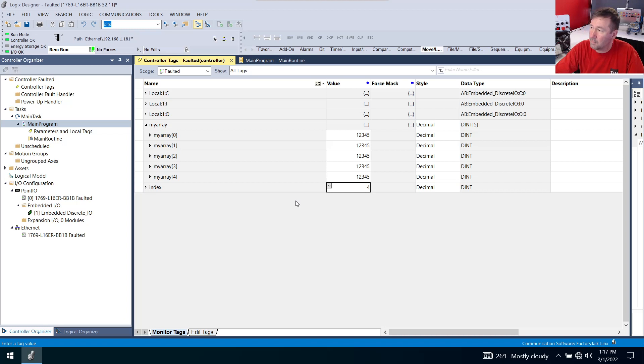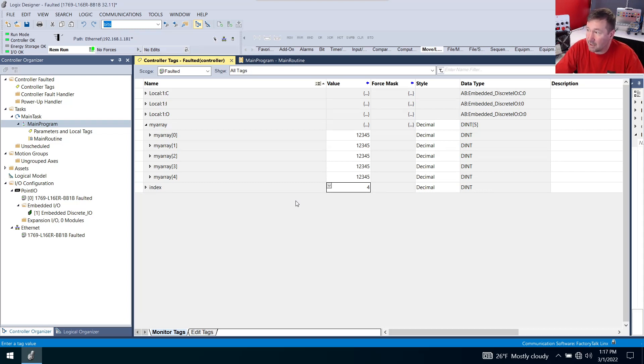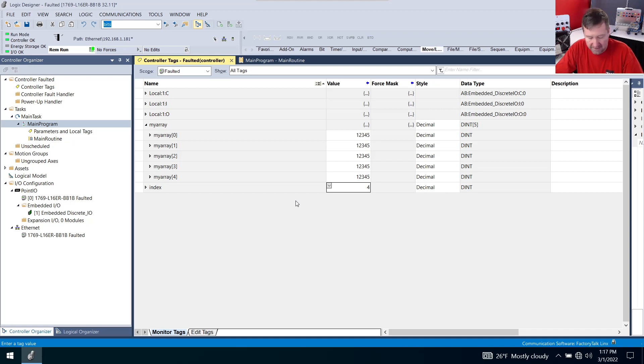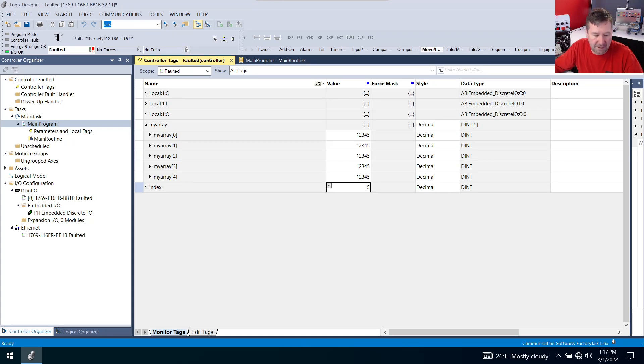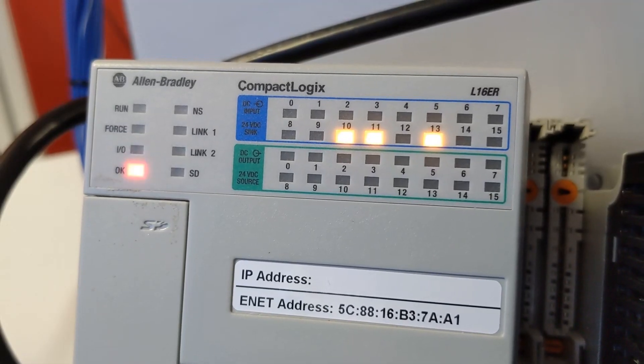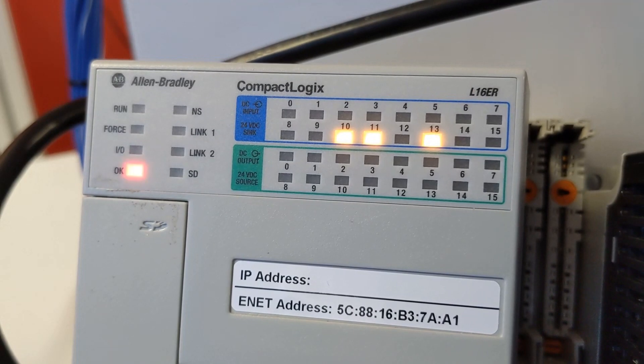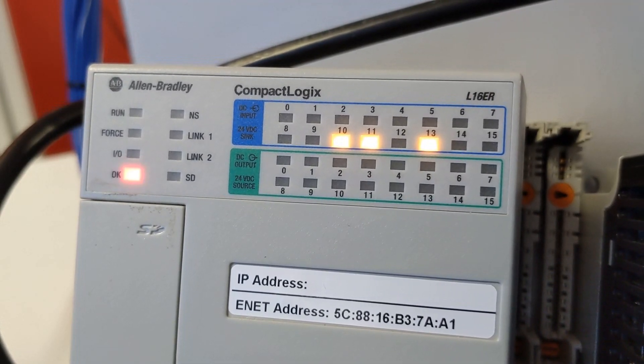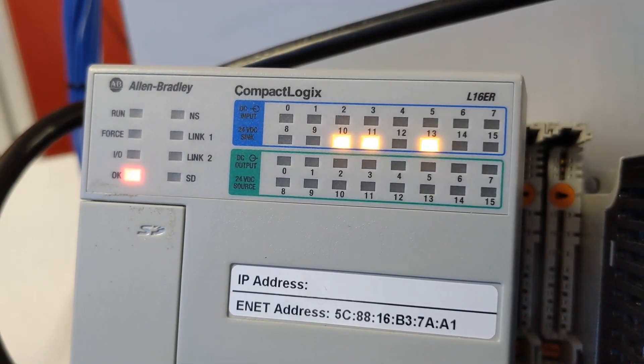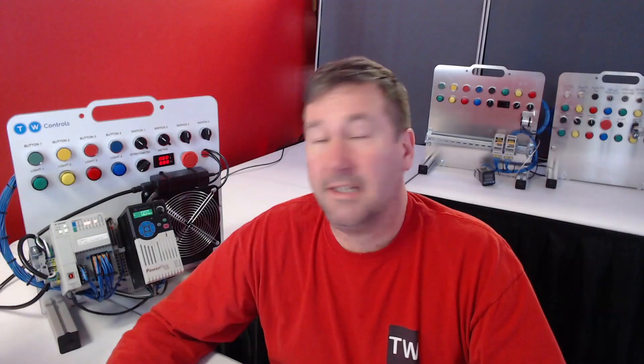And this next move is going to be the most common flashing fault that you will see out in the field. Now I'm going to move a value of five to it. Our controller fault indicator up here is flashing and we have a flashing fault light over here now. Also notice that our run LED is now out.